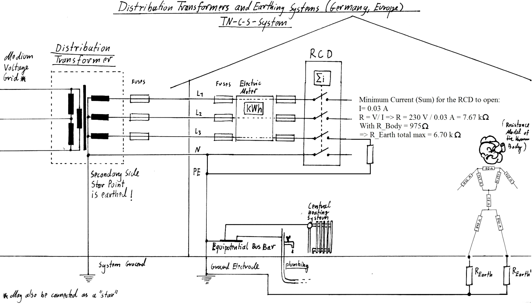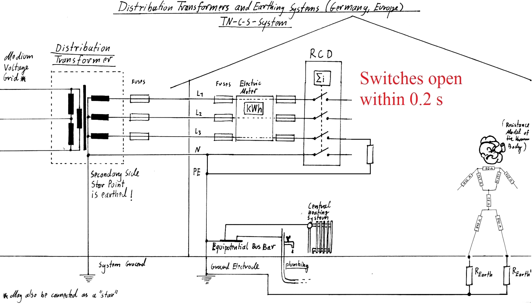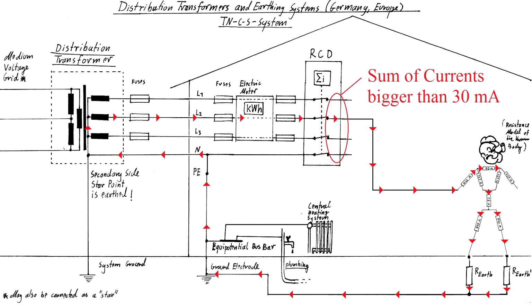This shows you that a ground with very high insulating capabilities will actually disable the RCD from reacting, while on the other hand it might limit a possible body current from being dangerous to you at all. The absolute time that an RCD should take to react is 0.2 seconds, but in most cases modern RCDs are much faster. The idea basically is that the RCD will disconnect you from the grid should you happen to touch one of the phases, as you can see here.